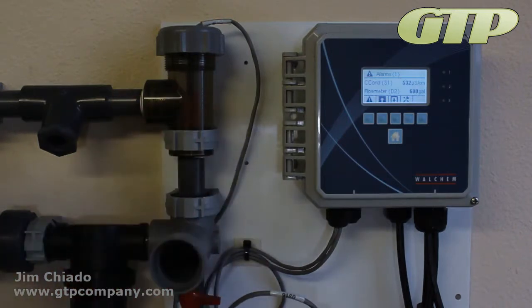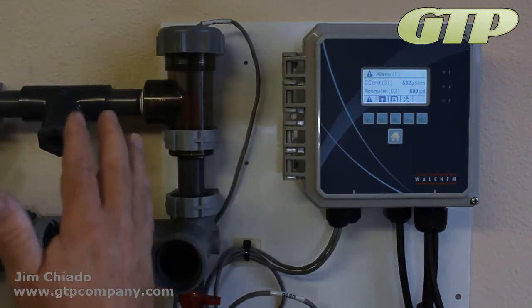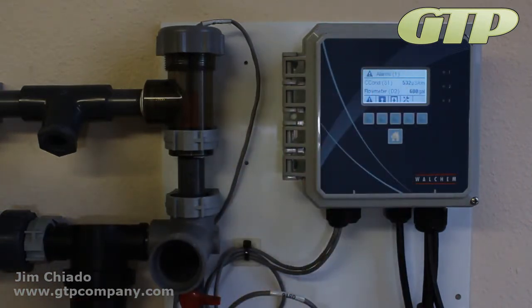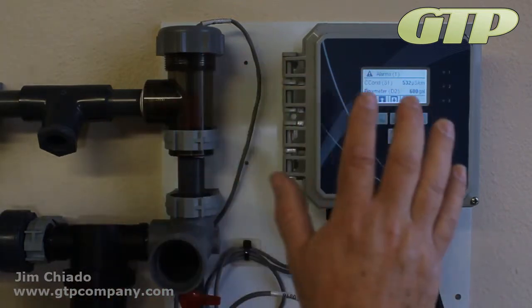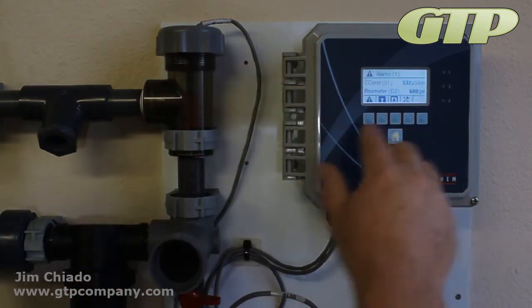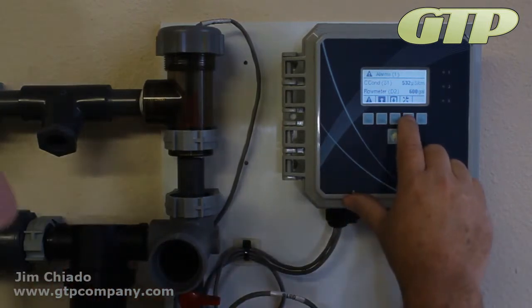You can have electrical noise, you can have all kinds of different things. This isolates it just to the controller, just to the system. Even if you don't have a calibration solution, just take some system solution. It's fine. Just take some water that you have there and use your handheld to verify the amount, or verify your conductivity level. It's all going to work out fine for you with typical cooling towers. So let's do a 1-point calibration. As we were doing it, if it was left in there, we would call that a 1-point process.